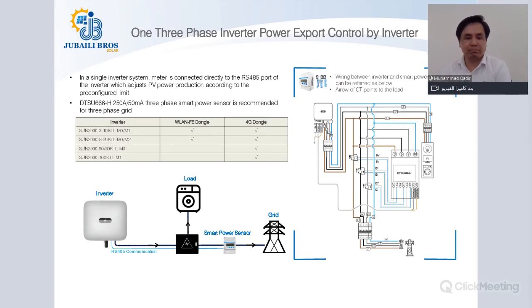So for one three-phase inverter, power export control is similar to the single phase. The only difference here is that you will have a three-phase smart power sensor from Huawei, which will be directly connected to the inverter. In case of three-phase, you will be using three voltage lines connected to the power sensor. Similarly, the three current transformers, which are supplied with the power sensor, you will connect to the smart power sensor. And this SLD is shown to you on the right side of the screen.